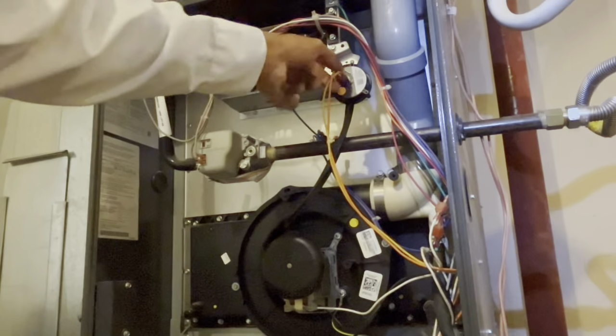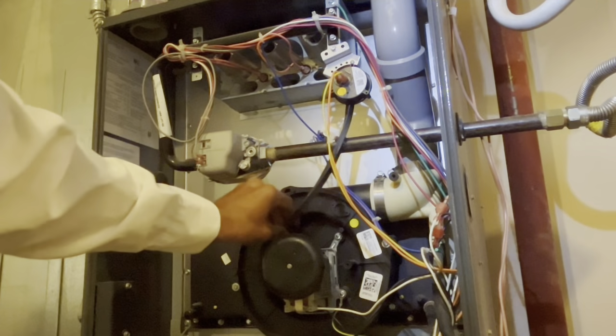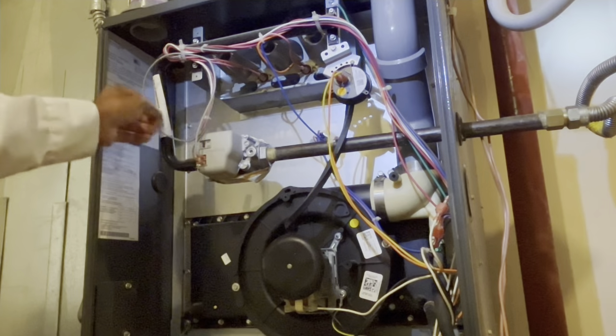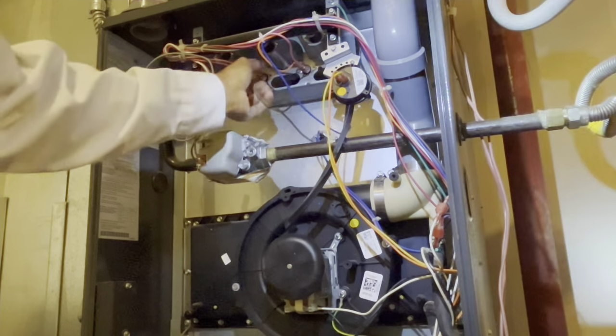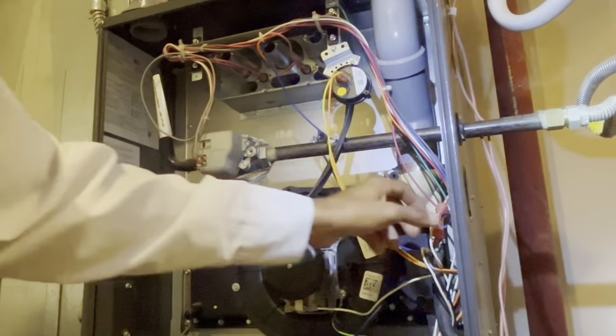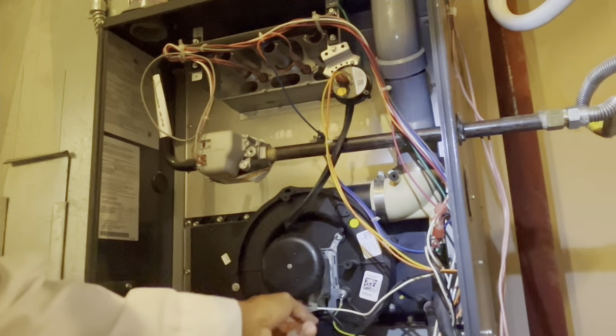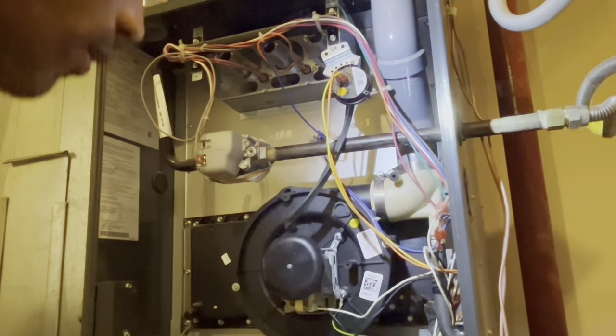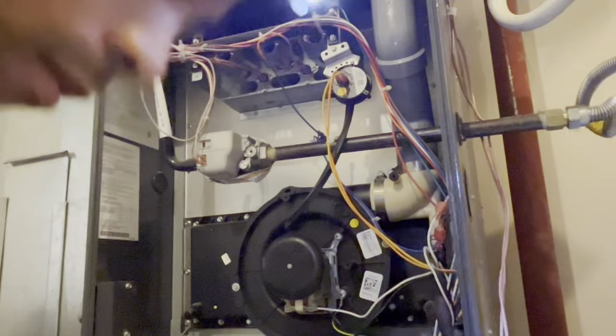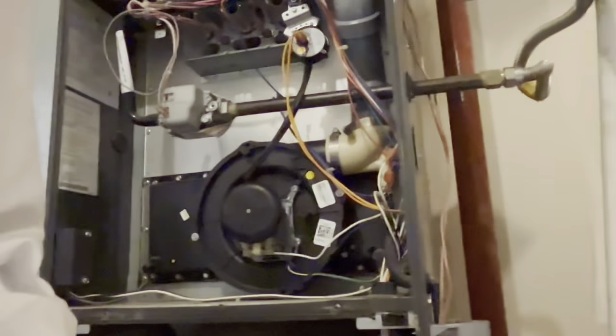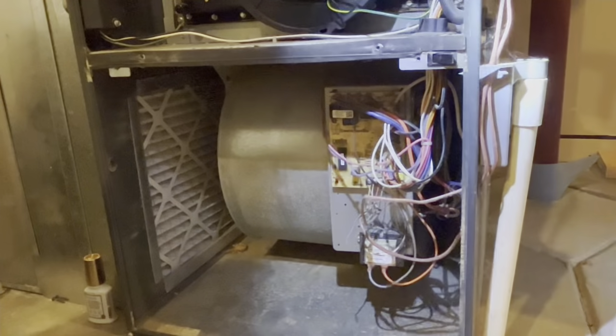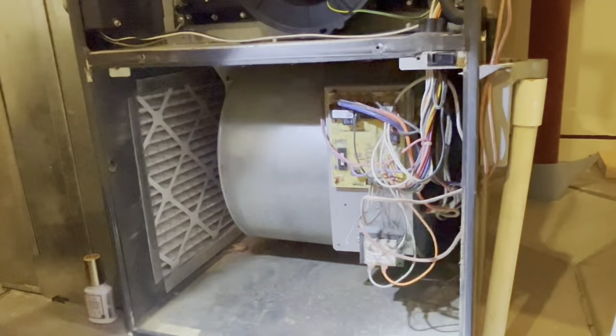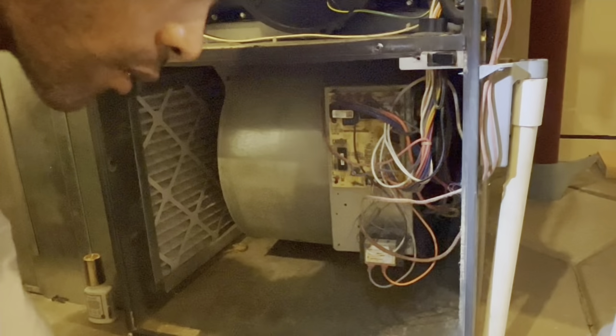So I'm going to get you in a little bit closer here. And I'm checking the safeties, the pressure switch, the vacuum line, all the electrical connections, making sure they're nice and tight, nothing is loose. I want to make sure that when it's running this winter that nothing causes a breakdown. That way it keeps the system running throughout the winter, because it does get about 0 degrees, or it gets kind of cold here. So the client will need to have a good furnace working.